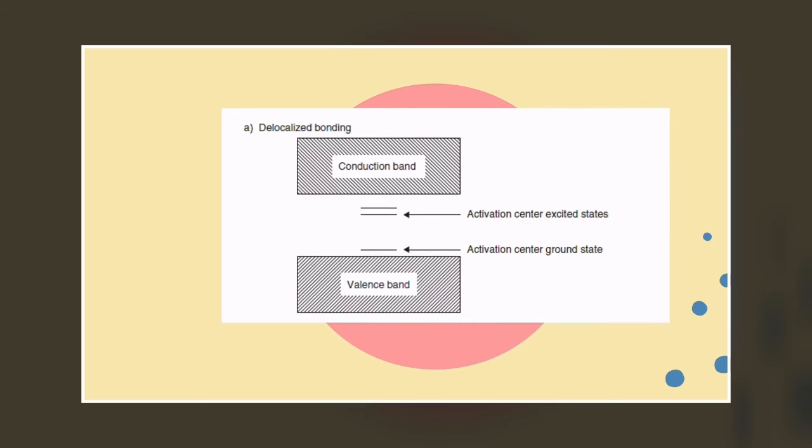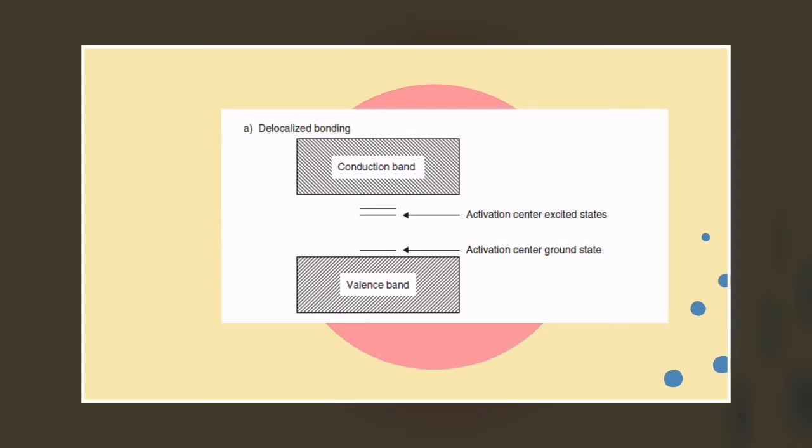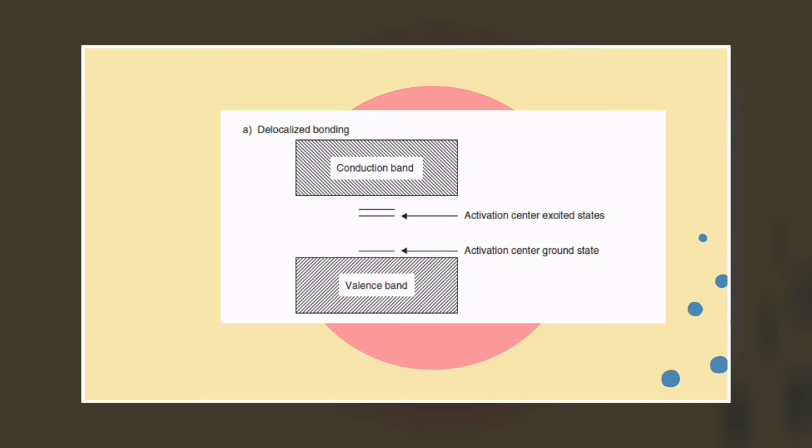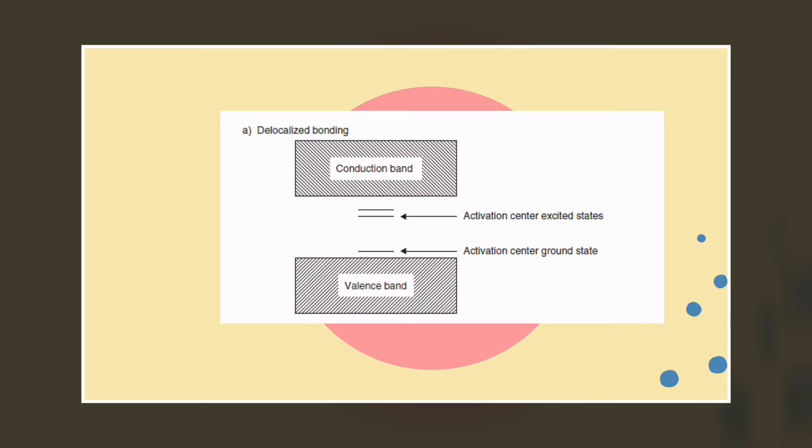When a sodium iodide crystal is kept without any radiation incident, all electrons stay in the valence band and there is no electron in the conduction band. However, when you place the crystal in the presence of some radiation, for example a gamma ray photon, the photon will impart its energy to one of the electrons of the crystal. This electron will gain a lot of energy and will move out, causing ionization and excitation.